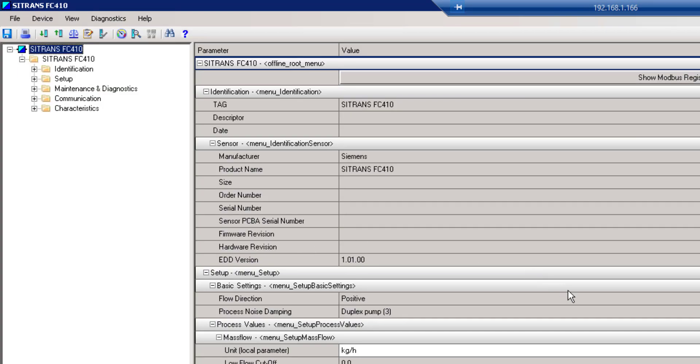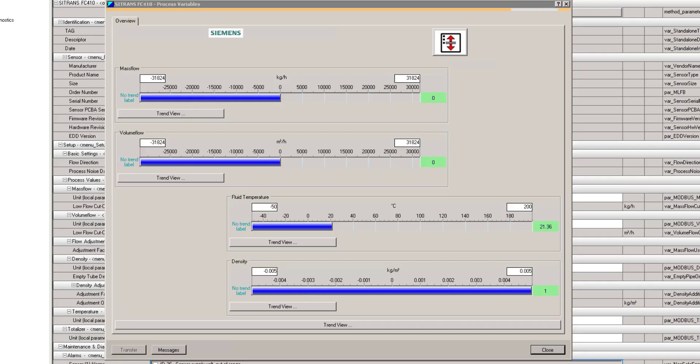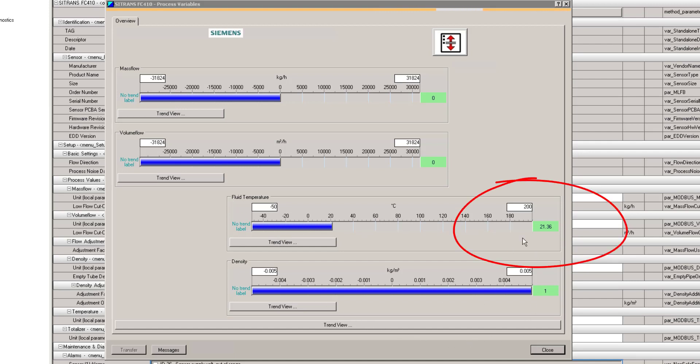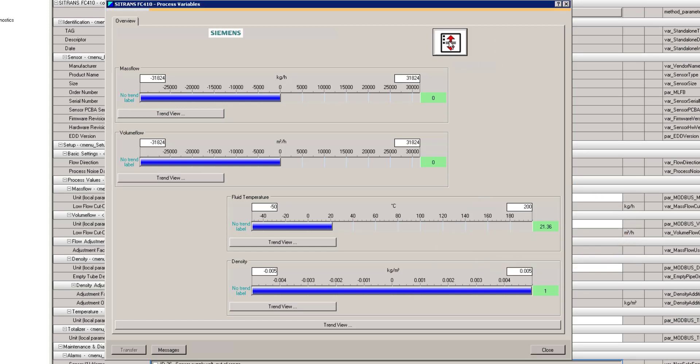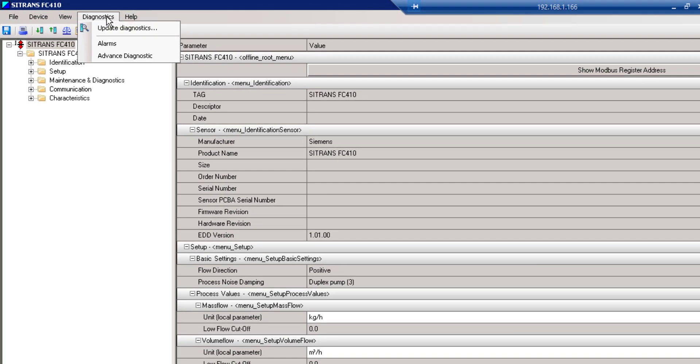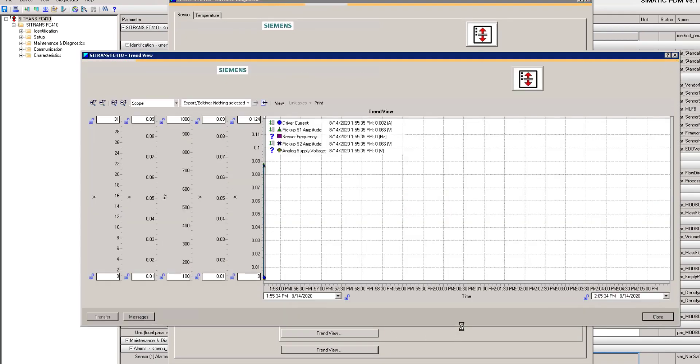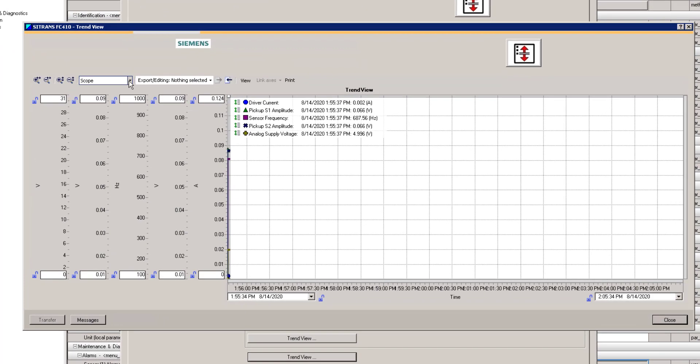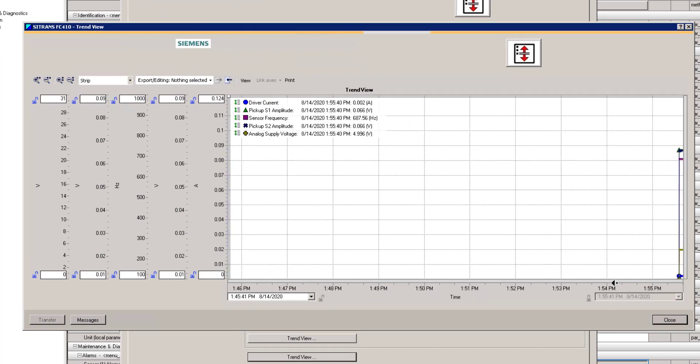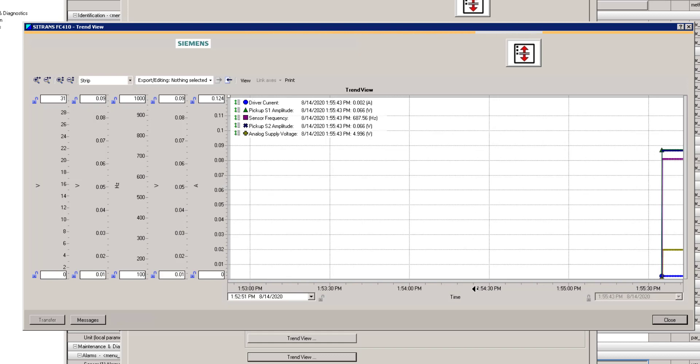To test the communications, I always just go onto the process variables. Once you've opened the process variable screen, you'll see here I've got a status alarm. The mass flow is zero. I always say focus on something you understand when you're looking at digital data for the first time. Well there's a built in temperature sensor, and I can see that coming back. If I want to update the diagnostics, I can just click on the icon here and update the diagnostics. We have full access to everything that we would over MODBUS 485 through the TCP to MODBUS 485 converter, including things like advanced diagnostics. So we can start looking at what is happening with my pickups coming from the Coriolis meter.